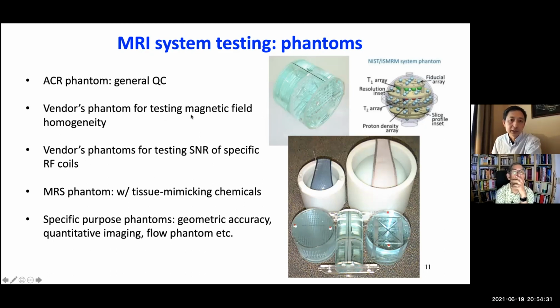And then for the magnetic field homogeneity, we need to use a large phantom that's usually provided by the vendor. Okay, so here is a large phantom that can be used to test the field homogeneity. And for RF coil testing, they are specially designed phantoms. Usually they are homogeneous phantoms, but with different shapes. So the purpose is to test various kinds of RF coils, for example, spine coil, body coil, knee coil, shoulder coil. You need to fit the shape of the coil. So that's why the phantoms are different, but they are basically all homogeneous.